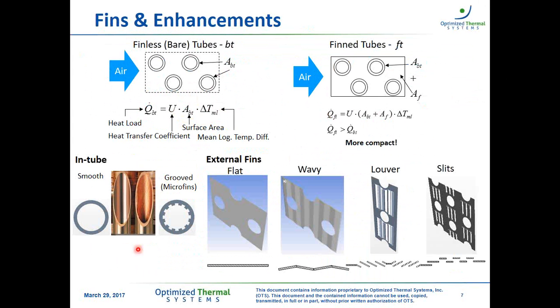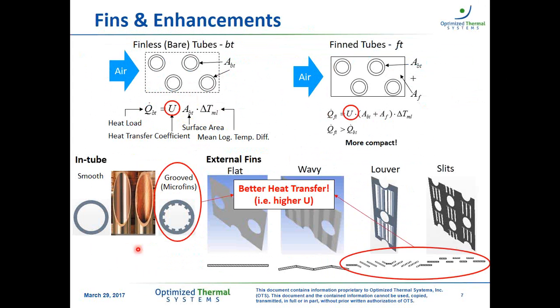So we talked about fins providing area, but we can improve even further the heat transfer by adding enhancements. And enhancements we can understand from the in-tube side as the microfins or the grooves. And from the fins or the air side, we have these two types here, louvers and slits, where we can see these cuts. And what they do is basically increase the U. So the fins provide surface area, and the enhancements provide higher U. And therefore, we increase even more the heat load.